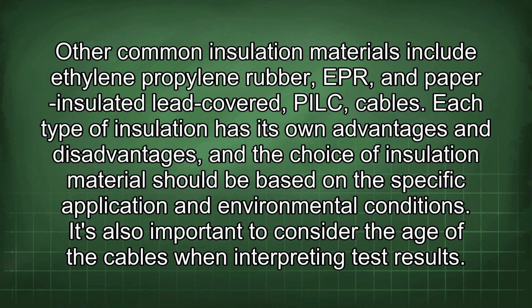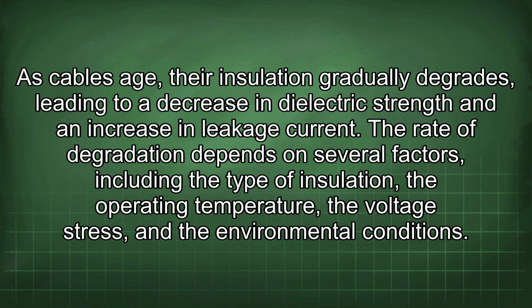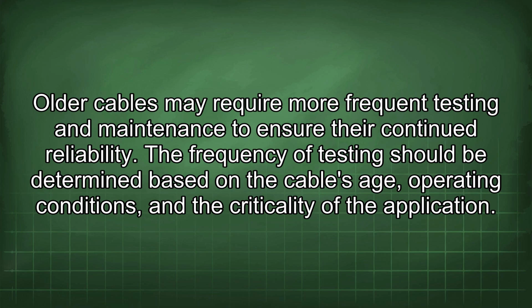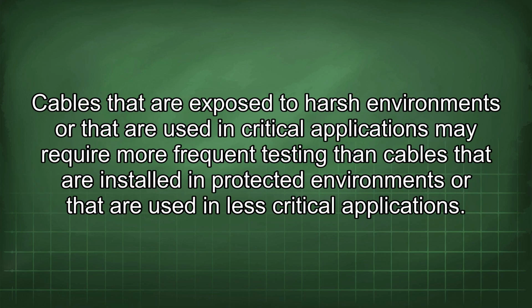It's also important to consider the age of the cables when interpreting test results. As cables age, their insulation gradually degrades, leading to a decrease in dielectric strength and an increase in leakage current. The rate of degradation depends on several factors, including the type of insulation, the operating temperature, the voltage stress, and the environmental conditions. Older cables may require more frequent testing and maintenance to ensure their continued reliability. The frequency of testing should be determined based on the cable's age, operating conditions, and the criticality of the application. Cables that are exposed to harsh environments or that are used in critical applications may require more frequent testing than cables that are installed in protected environments or that are used in less critical applications.